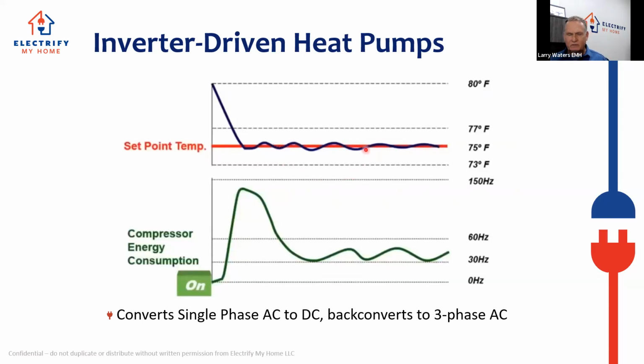And when we get done with the tempering phase is the point where everything in the house is 75. All the walls, floors, doors, and countertops, everything is now 75 degrees. And then the unit slows down even further. And this is what we call the thermal equilibrium stage. And once our house is at thermal equilibrium, it starts acting as its own storage battery. And so our house is a storage battery. And so if it runs for hours and hours and hours on this thermal balance point versus a few hours at this, it's going to use far less energy here. Typically, on a house that we do that's under 1,500 square feet, this is going to be slightly more than a hairdryer on high speed, depending on how good of a hairdryer you have at your house, about 1,850 to 2,000 watts. And down here, it's going to be using 250 to 300 watts.